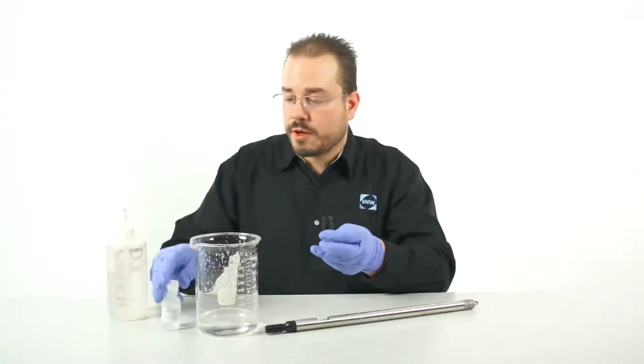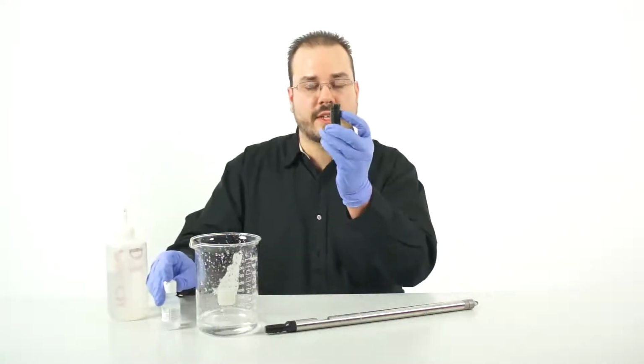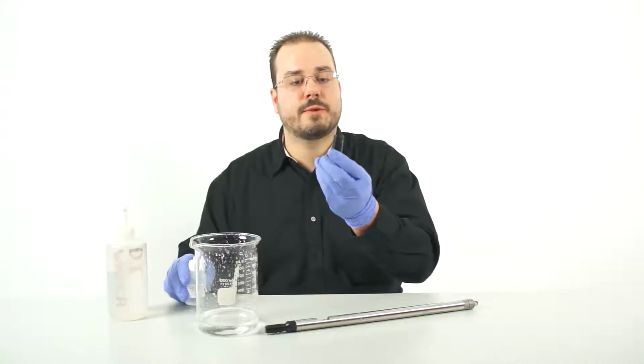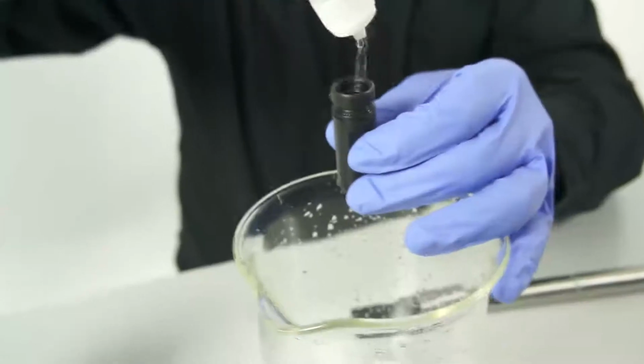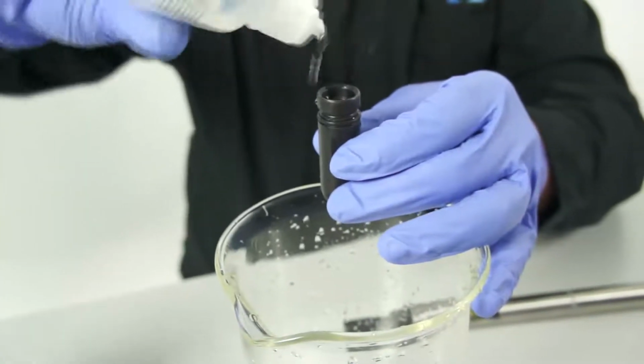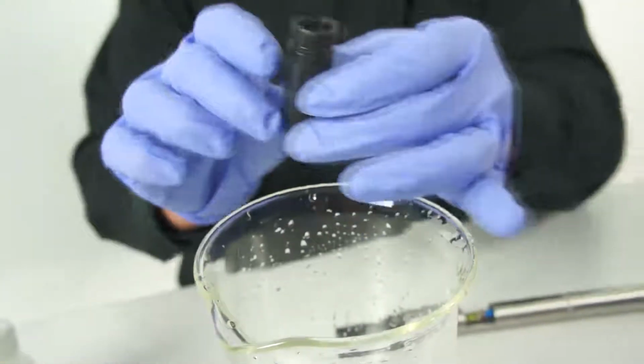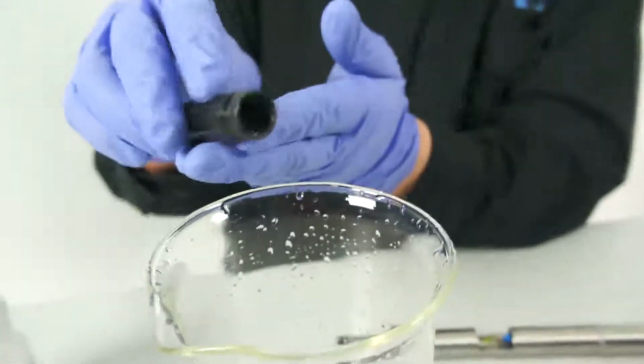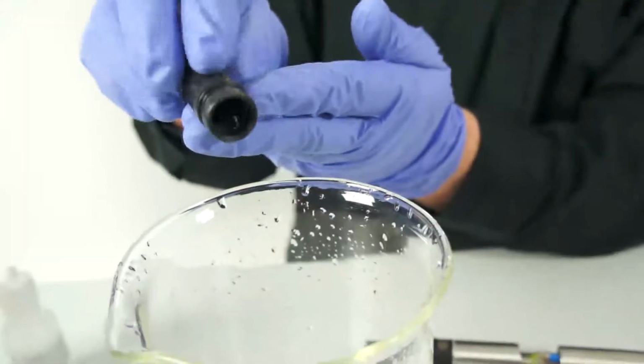After flushing with DI water, we want to make sure that the O-ring is in its lower position to keep the liquid junction ports open. Pour a small amount of reference electrolyte into the cap and roll it through the threads to flush out any remaining DI water.